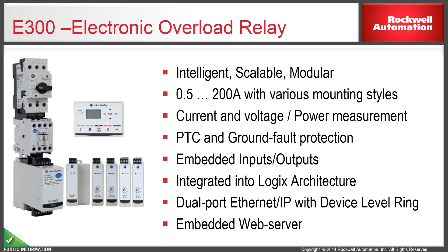From 0.5 to 200 amperes, there are various mounting styles available. You have current and voltage measurement. You have PTC and ground fault protections. You have certain inputs and outputs embedded into the relay itself. In addition to that, if you want more IOs, expansion IOs are also available, so you can add on. It directly is in the Logix architecture on Ethernet. Dual port Ethernet IP is built into the relay itself, so it can help you with device level ring topology, right? You can deploy any star, ring, or DLR, and it has an embedded web server which will give you real-time information across all the locations.